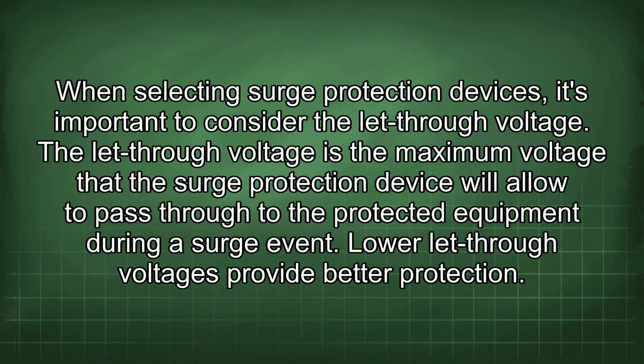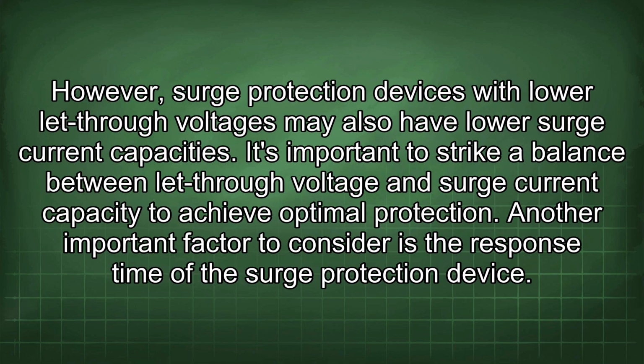When selecting surge protection devices, it's important to consider the let-through voltage. The let-through voltage is the maximum voltage that the surge protection device will allow to pass through to the protected equipment during a surge event. Lower let-through voltages provide better protection. However, surge protection devices with lower let-through voltages may also have lower surge current capacities. It's important to strike a balance between let-through voltage and surge current capacity to achieve optimal protection.